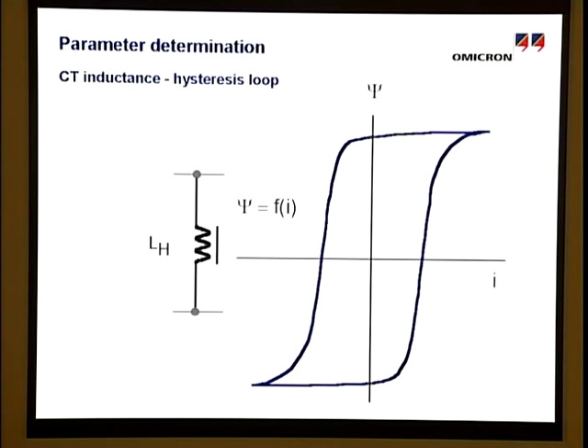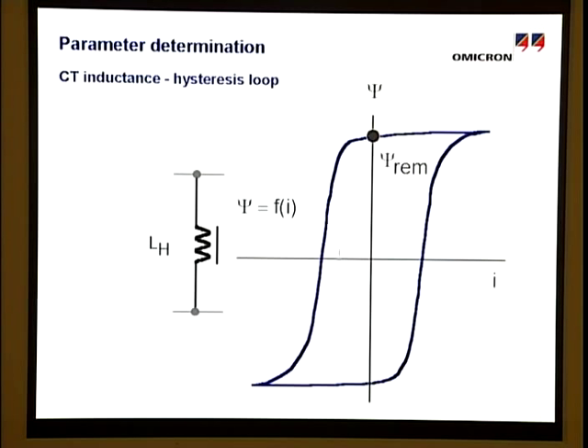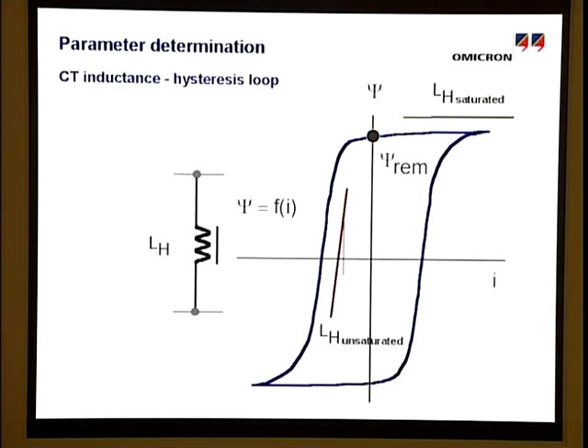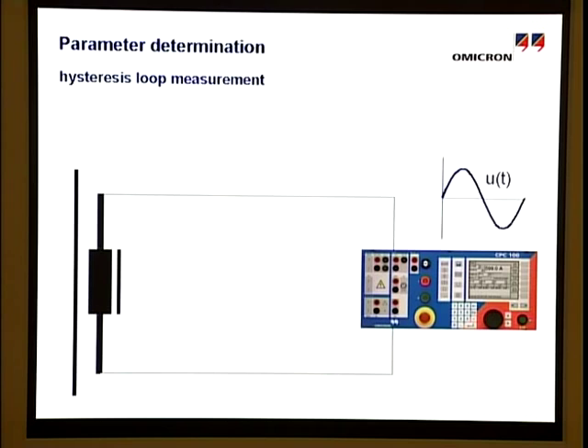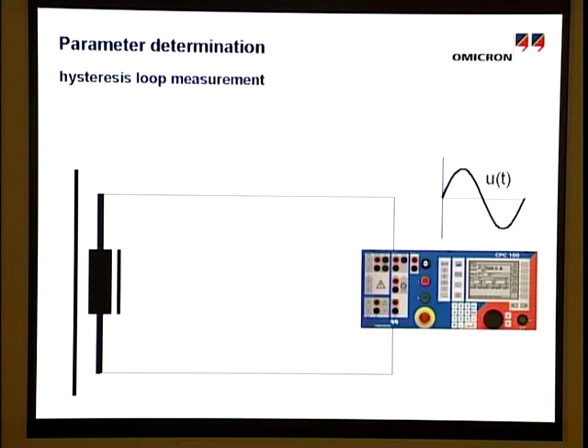Remanence, non-saturated and saturated magnetizing inductance are characteristic parameters which are often only available with difficulty. Because of this, the following procedure for direct measurement via relay test equipment was developed. A sinusoidal voltage is connected to the secondary transformer terminal. The primary test system, CPC100, designed particularly for CT and VT testing, is ideal for this.